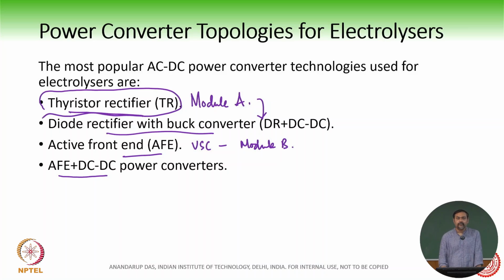The reason we use thyristor rectifiers is because of the high current - as I told you, currents can reach 2500 amperes. The thyristor rectifier is one of the most robust converters, and it can carry or withstand short circuit current for a long time, which is not possible with IGBTs or MOSFETs - they cannot withstand that current. So thyristor rectifiers have been a very popular choice for electrolyzers.